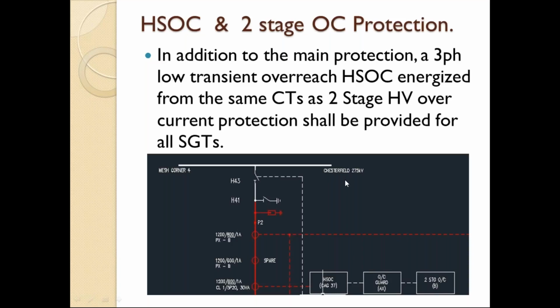It is for 275 kV, and it is a mesh corner protection. So they have used HSOC, high set overcurrent, and overcurrent guard, and there is a two-stage overcurrent protection. So what is the purpose of giving this, normally in the existing relays they will be using IDMT.